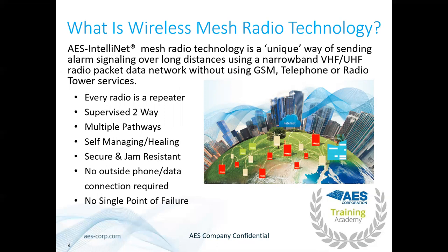One of the good parts about the new 2.0 subscribers is that they are secure and jam resistant. The username and password protects the programming so somebody else can't come along and steal your subscriber. With the legacy model 7788, if you replaced the transceiver and put in your account ID and cipher code, that basically became your subscriber. With the new 2.0 radios, you will need a username and password. The default is admin/admin, so I'd highly recommend you change it. There's no outside phone or data connection required — this is a dealer-owned and operated network. It will work forever.